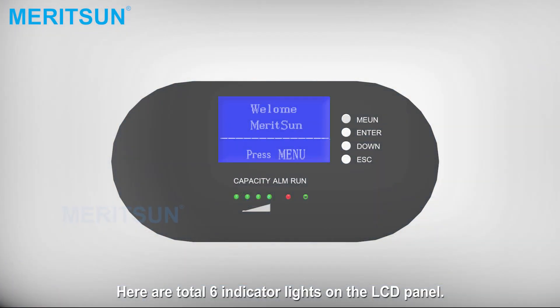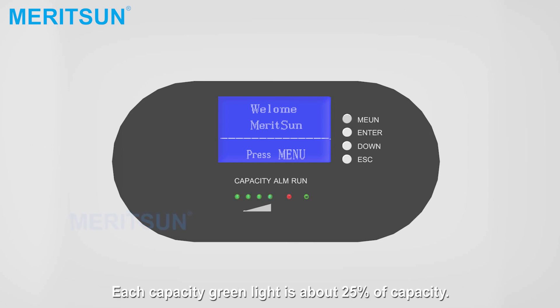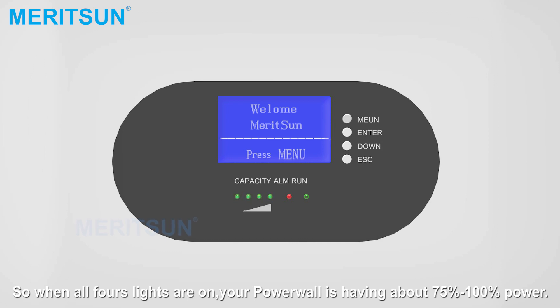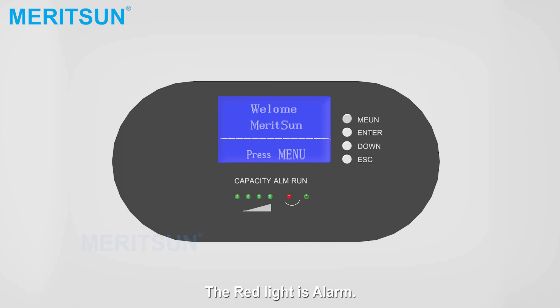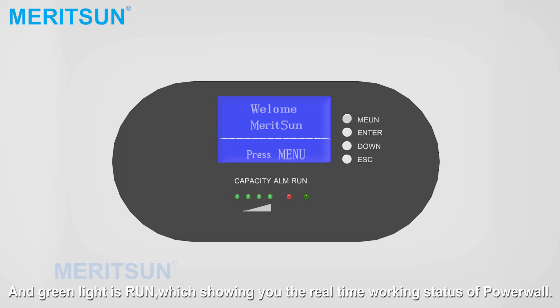There are a total of 6 indicator lights on the LCD panel. Each green capacity light represents about 25% of capacity, so when all 4 lights are on, your Powerwall is at about 75% to 100% power. The red light indicates alarm, and the green light indicates run, showing you the real-time working status of the Powerwall.